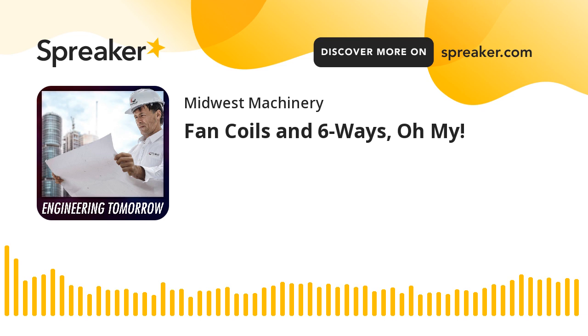So hold on. When you talk about these valves, where will you find them in your system? They would be the feed valve attached to or very close to the fan coil itself. And they're primarily on fan coils. We probably will eventually get to putting them on a blower coil, which is more of a challenge because you've got a bigger unit, bigger CFM, and higher water flow, and we're not sure the orifice sizes in six-way valves will be workable in all applications. We're starting with the fan coils right now.